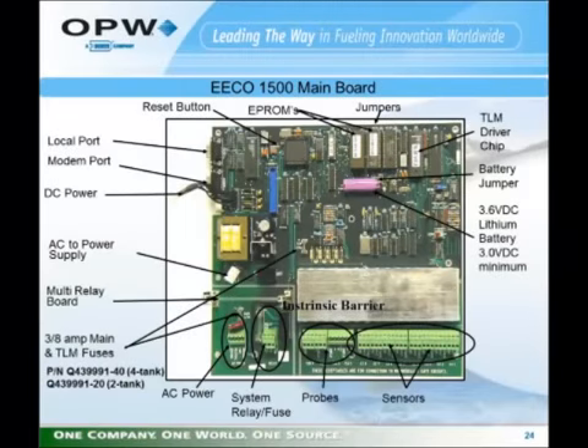On the EECO 1500 main board, in the layout that we show here, you can see that the AC power is in the lower left corner. Above the AC power connection and the relay connection is a slot to install an optional 4 relay board. Above that 4 relay board, you'll see a transformer and what looks like power supply circuitry. That is the power supply for the probe voltage. But above the transformer on the left-hand side of the board, you'll see some black wires that are labeled DC power. This is the power input to the main board from the external power supply that's mounted on the chassis.